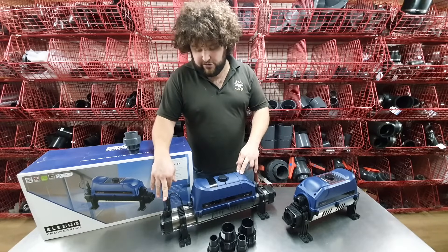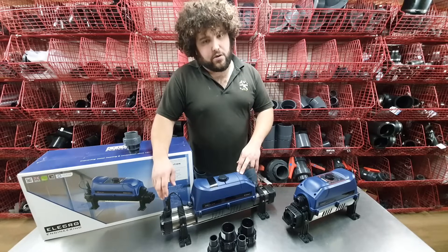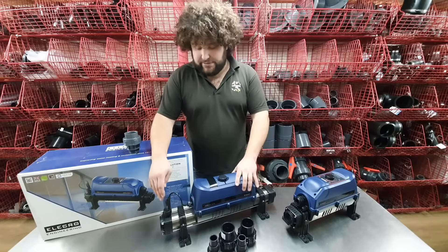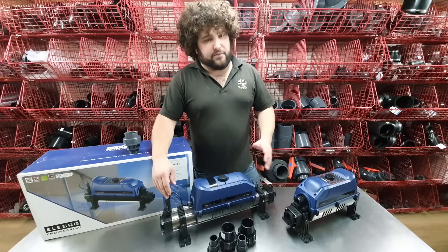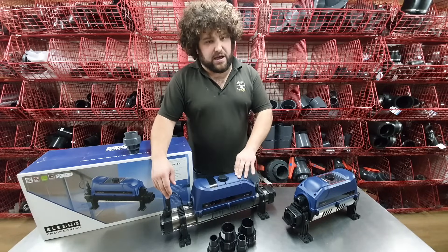You've got your float switches here — it's an ultra-reliable flow switch, and they can sense from one cubic meter an hour, or a thousand liters an hour, up to 17,000 liters an hour. So that's your minimum and maximum flow rates.